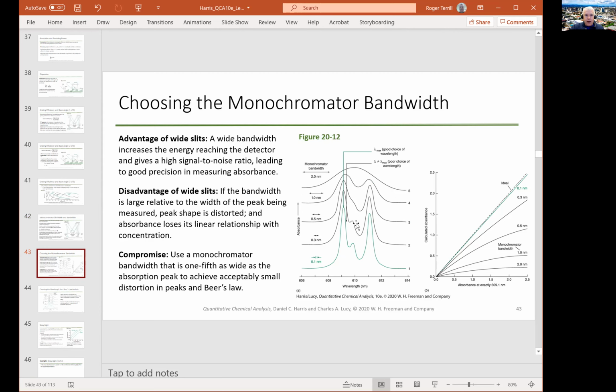And then you come down by another factor of almost 2 here, and you can clearly see this third peak, right? And so when the effective bandwidth is at a tenth of a nanometer, a factor of 20 lower than it was up here, then you can clearly see that what looked like 1 peak is actually 3. And so this could easily resolve, say, the existence of a different chemical species, or give you more details about a given species or something like that.